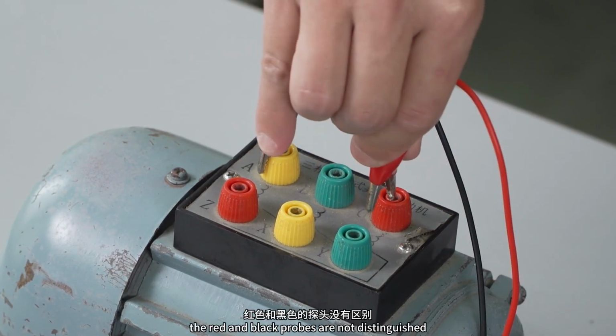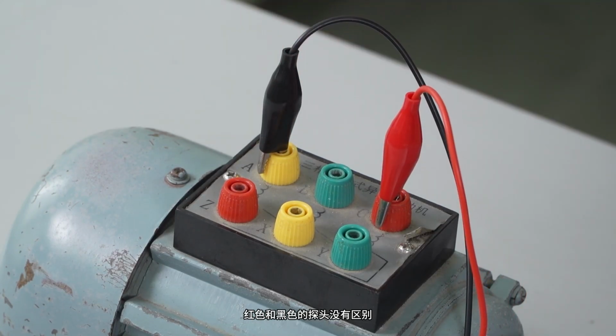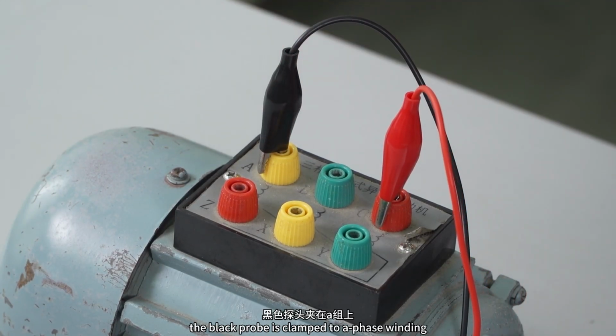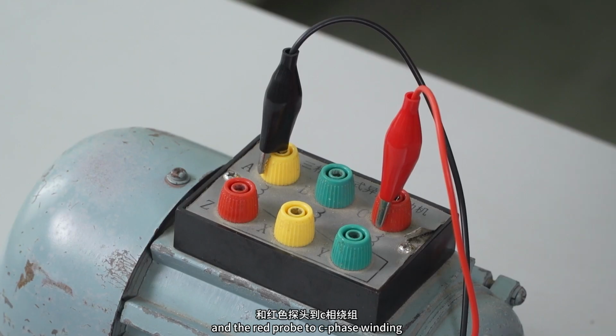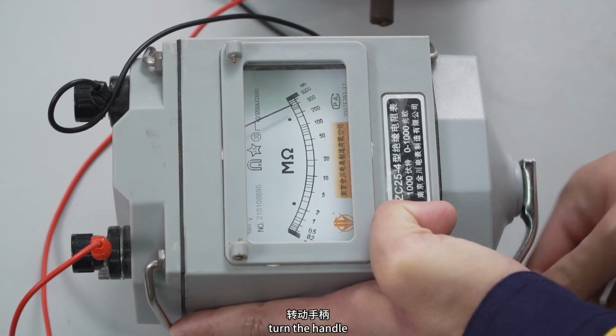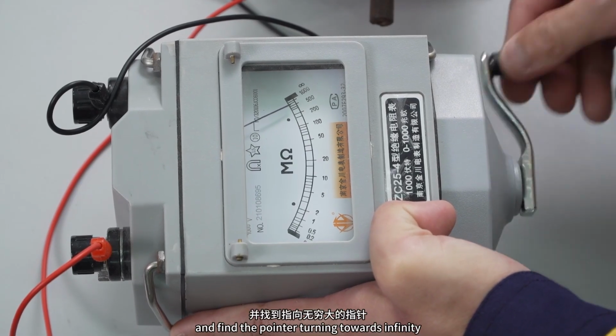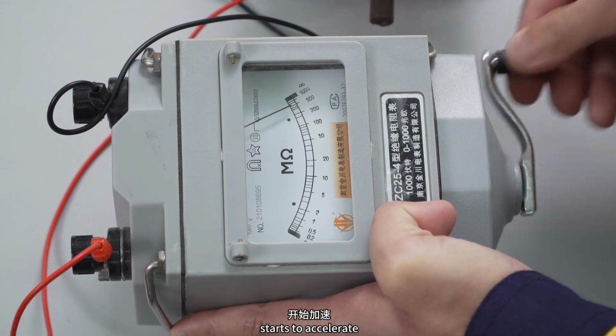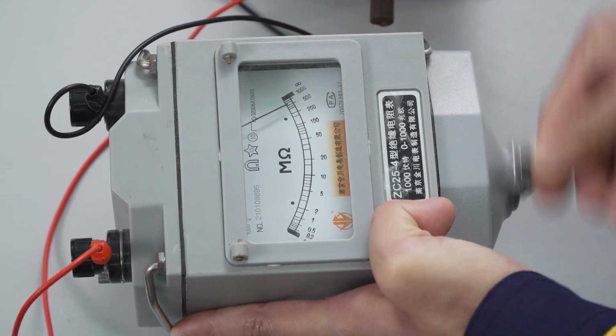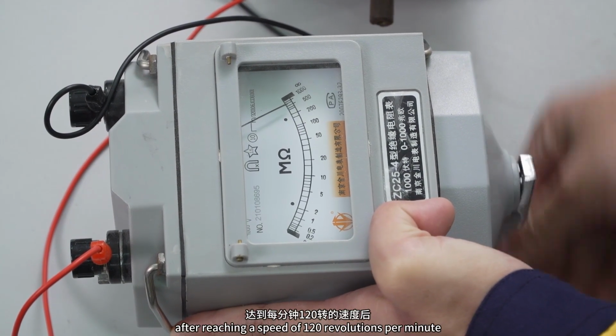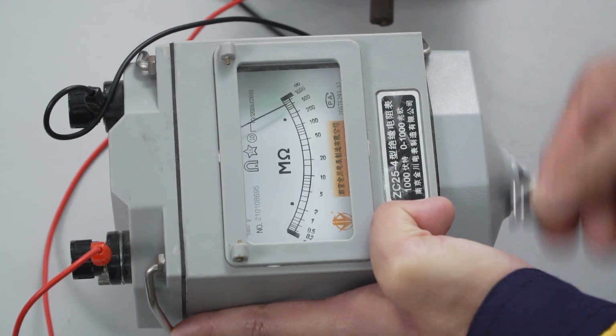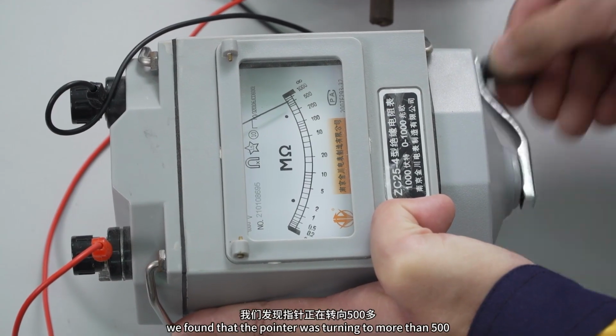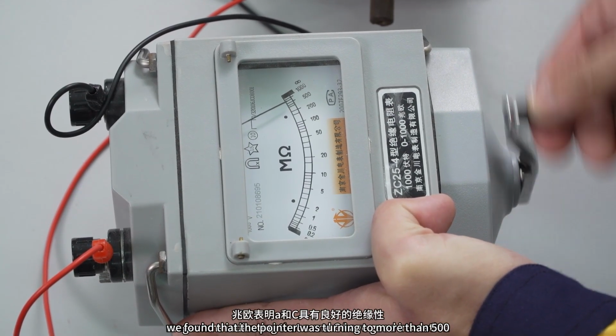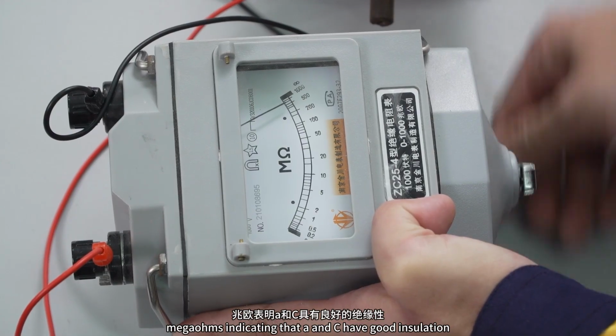When measuring, the red and black probes are not distinguished. The black probe is clamped to the A phase winding, and the red probe to the C phase winding. Turn the handle, and we find the pointer turning towards infinity. Starts to accelerate. After reaching a speed of 120 revolutions per minute, we found that the pointer was turning to more than 500, indicating that A and C have good insulation.